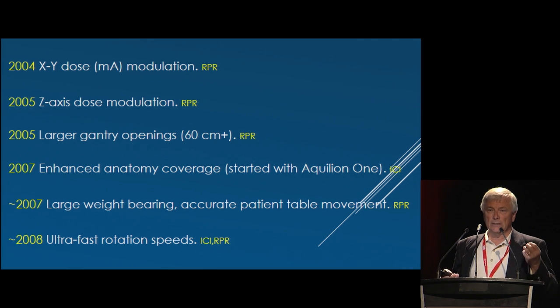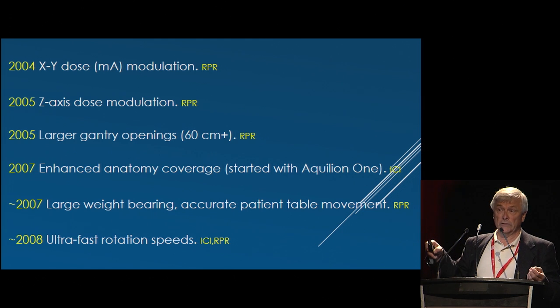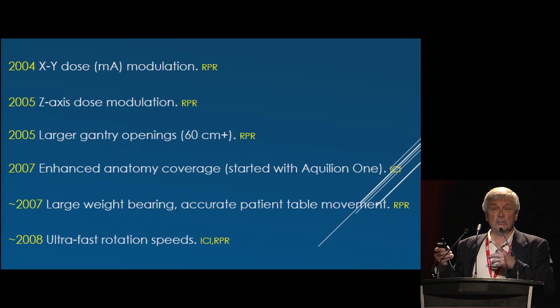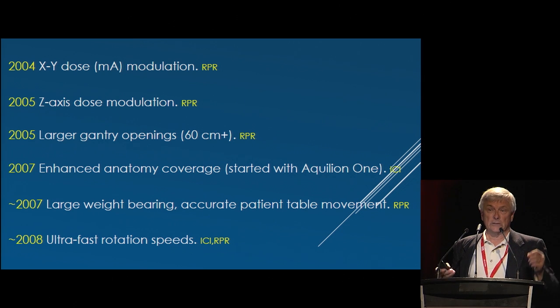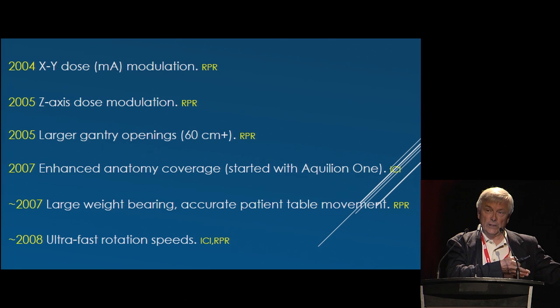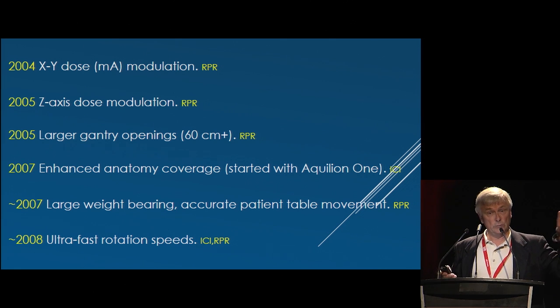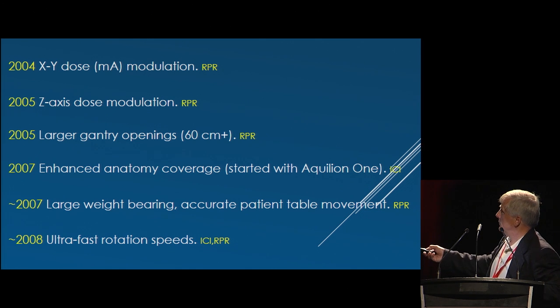They're taking literally tens of millions of data points from all the different detectors. There's 1,000 detectors that are rotating 4 times a second, and each detector is being chopped or accessed or read a few thousand times a second. So there's an enormous amount of data, and this is why when we have now even faster computers, we can start doing things like iterative dose reduction, because we can start working on that raw data, which is in the millions or the tens of millions. So 2008, ultra-fast rotation speeds.